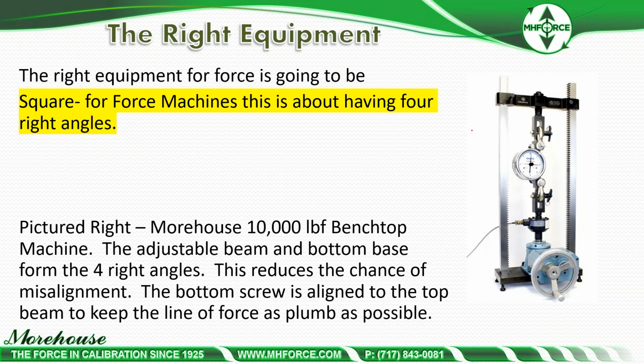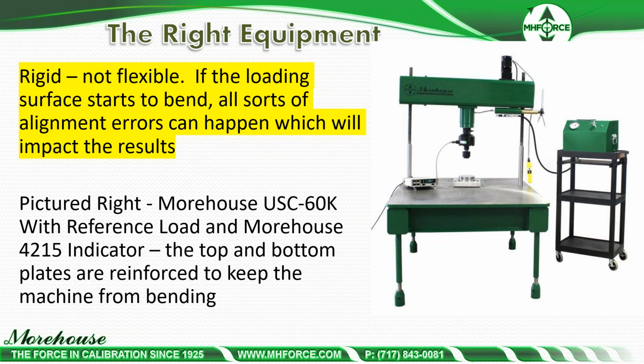We are using alignment adapters per ISO 376, which overcome about 0.1 degree of misalignment. So we feel like we get everything good, and we're also doing some other things, as shown in the next picture after this one. But rigid means not flexible. If the loading surfaces start to bend, all sorts of alignment errors can happen, which will impact the results.